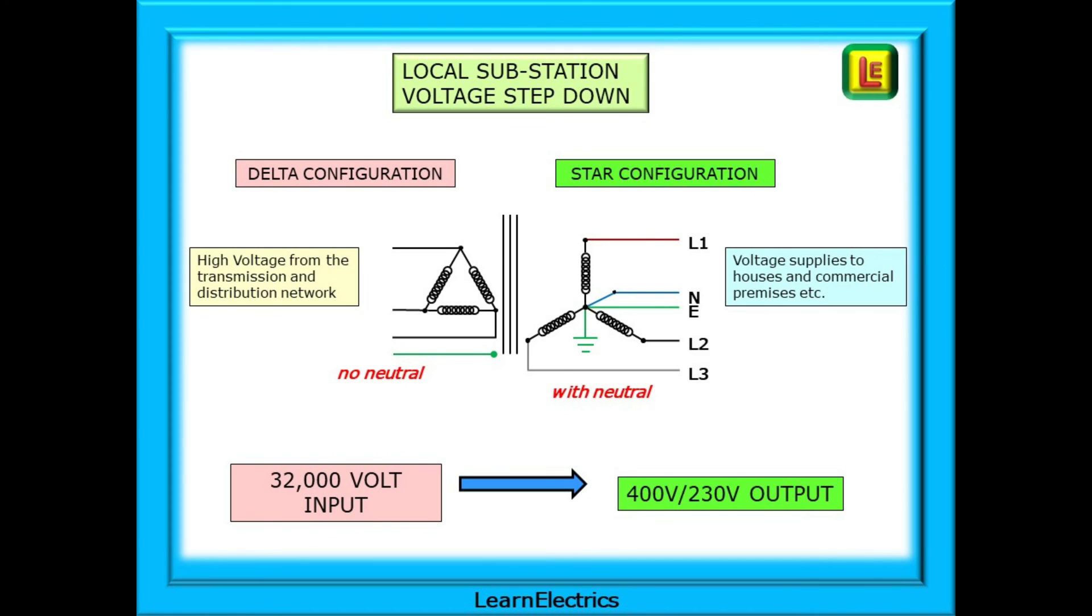The other side, the right hand side, is wired as a star configuration. All three windings are connected at a central point called the star point. The earth is also connected at the star point and we now have a neutral connection also at the star point. So we have three phases L1, L2 and L3 plus neutral plus earth. This is a step-down transformer, so our output voltages will be 400 volts three-phase and 230 volts single-phase.